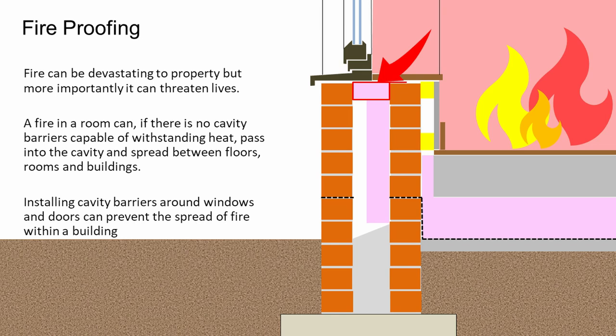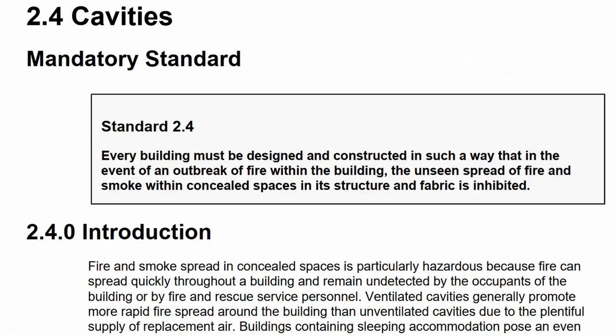Fire in a room can, if there are no cavity barriers, jump from the room into the cavity and spread between rooms and different buildings. The Scottish Building Regulations, Regulation 2.4, Standard 2.4, states that every building must be designed and constructed in such a way that in the event of an outbreak of fire within the building, the unseen spread of fire and smoke within concealed spaces in its structure and fabric is inhibited. The key point is unseen spread of fire in concealed spaces — they're really talking about various cavities within the building.